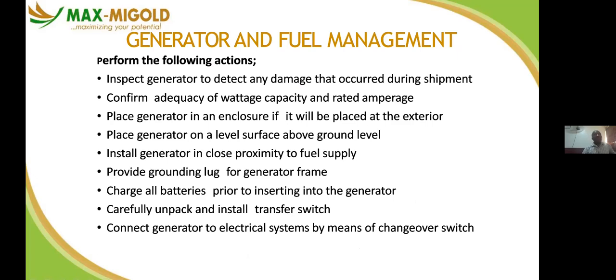So we have generator and fuel management. Why do you need to manage your fuel? You manage your fuel so that you can prolong the lifespan of your generator. A bad diesel will contaminate your generator. It will spoil the injector, the nozzles, and so on. So you start wasting money trying to fix your generator instead of paying detailed attention to the diesel supply to your site. So inspect the generator to detect any damage before installation.